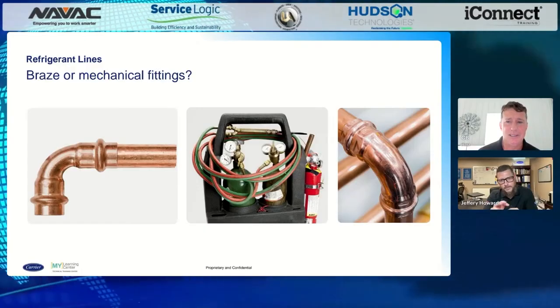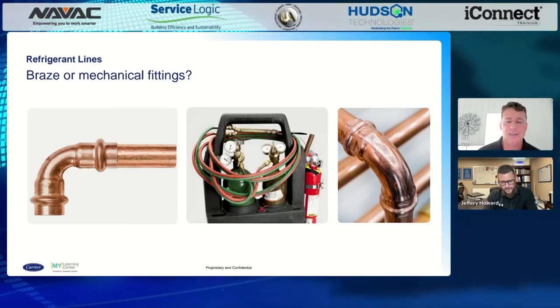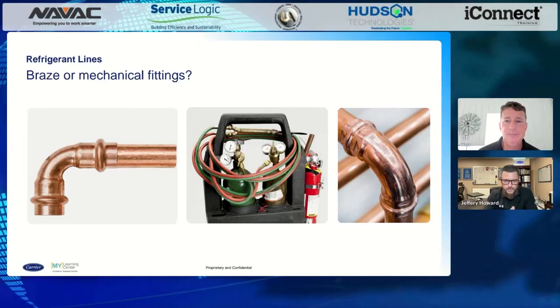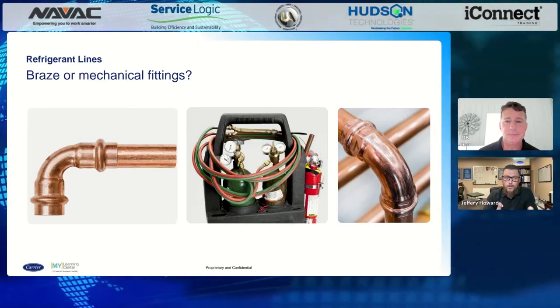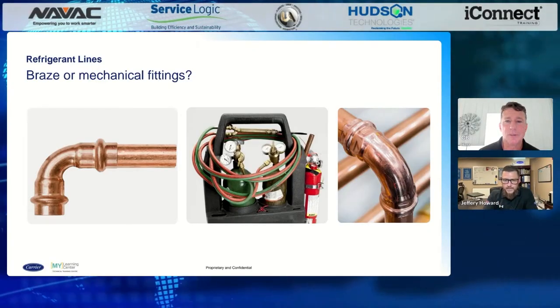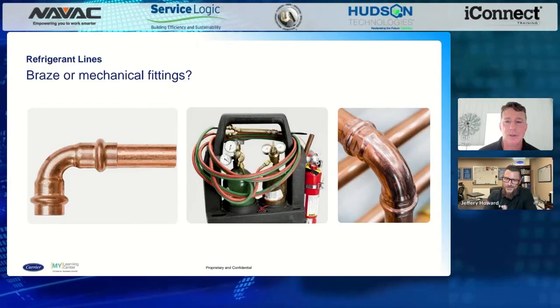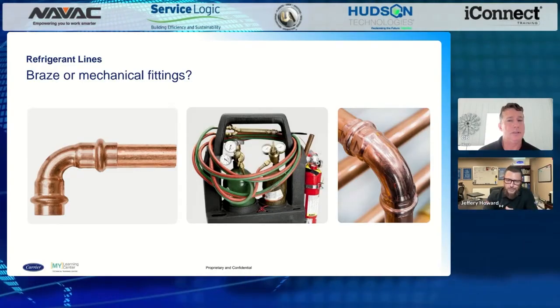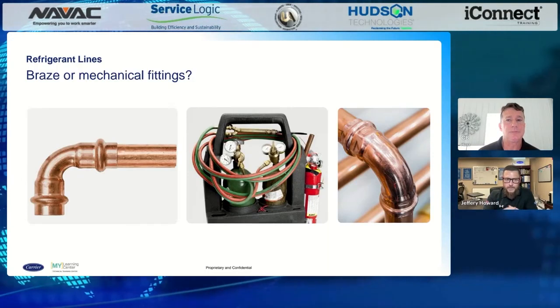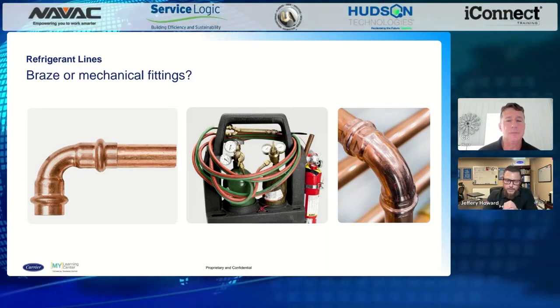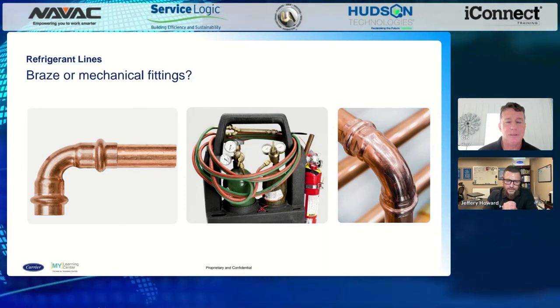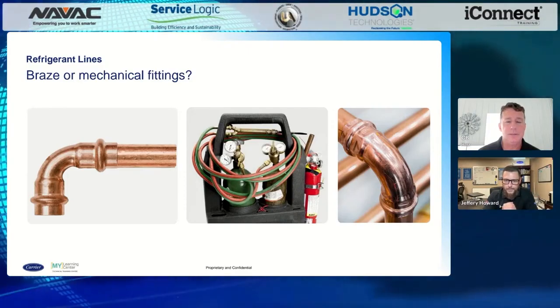Instead of having the bell, you can put the bell on there if you want—if you're going to braze, you can clean the end of your service valve, swage it, and get your bell back. Or if I'm using mechanical fittings, I can go ahead and press directly to it without trying to cut a bell off. Just one of the small things we've done to help out the field and the technicians installing or working on it.